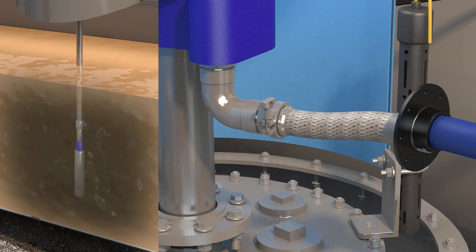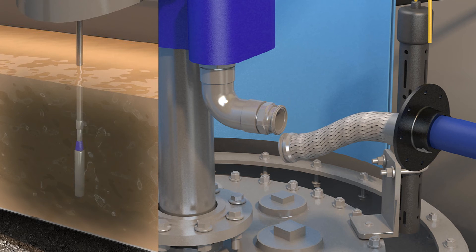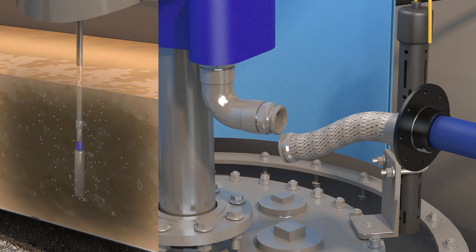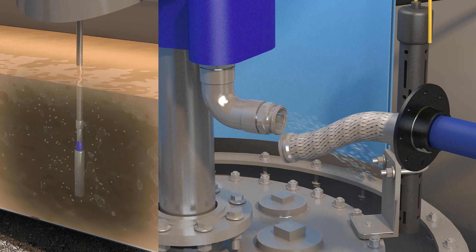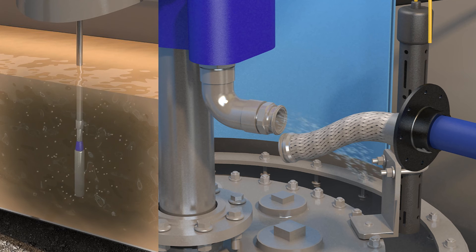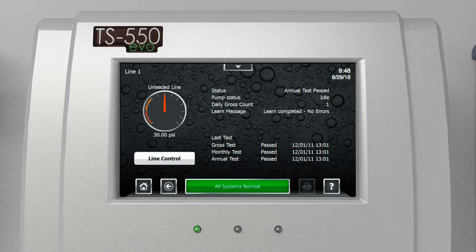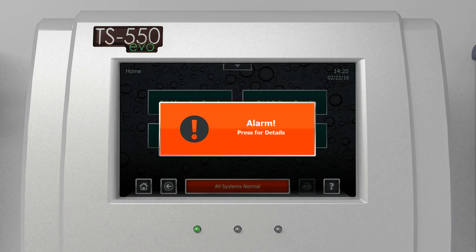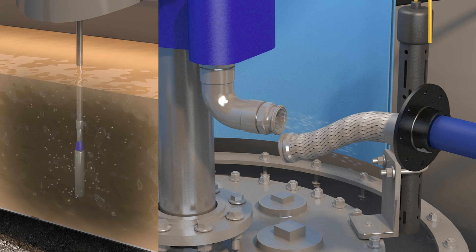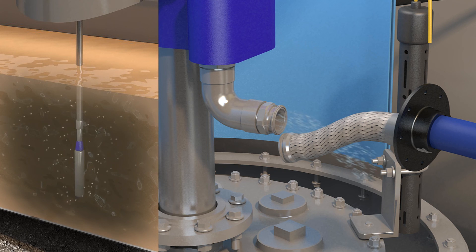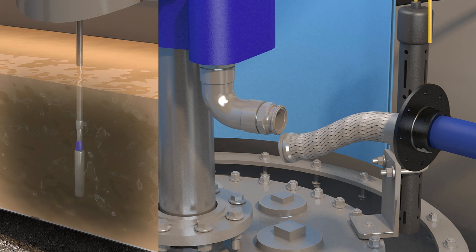A real-world example: a technician on site forgets to fully connect or tighten a flex connector, which may leave a leak path. Our electronic line leak would power the submersible to pressurize the line. Once the submersible shuts off, we start watching the pressure and look for our learned pressure decay. If the decay exceeds our learned threshold, we alarm and shut down the line. Simply put, our leak detection system can handle larger sites with longer piping and more demand.